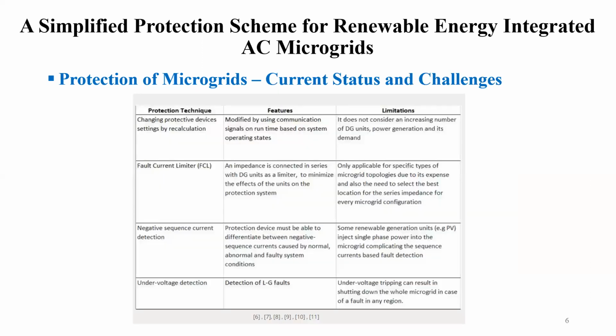So overall, we present some of the current status and challenges that are there. For example, if we look at the fault current limiter, the limitations are that it is only applicable for specific types of microgrid topologies, because of its expense, and also the need to select the best location for the series impedance of a microgrid. Similarly, with undervoltage detection, undervoltage tripping can result in shutting down the whole microgrid in case of a fault in any region. So these are certain challenges associated with the currently existing protection techniques.